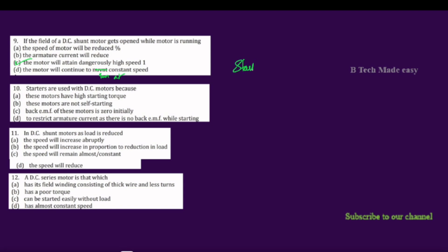The main function of a starter in a DC motor is to limit the starting current and to protect the armature. We use starters to restrict the armature current because there is no back EMF while starting. The starter limits or reduces the current since back EMF is absent at startup. This is how starters are used.